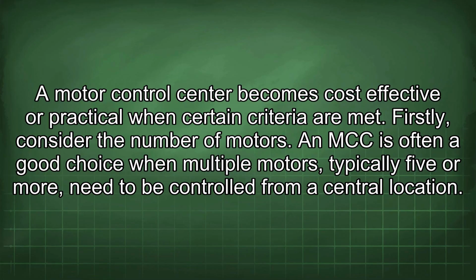A motor control center becomes cost-effective or practical when certain criteria are met. Firstly, consider the number of motors. An MCC is often a good choice when multiple motors, typically 5 or more, need to be controlled from a central location.